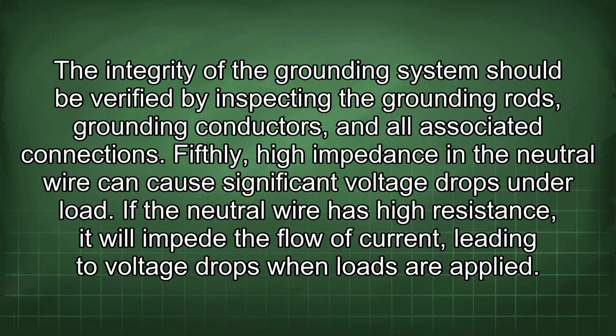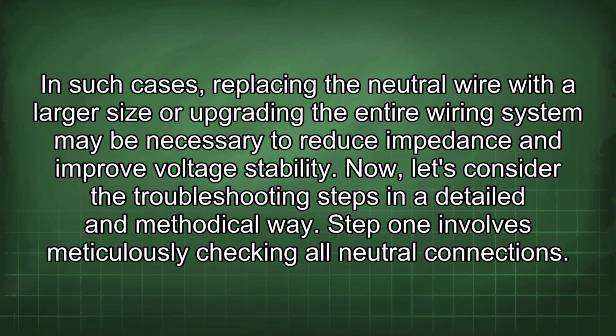Fifthly, high impedance in the neutral wire can cause significant voltage drops under load. If the neutral wire has high resistance, it will impede the flow of current, leading to voltage drops when loads are applied. In such cases, replacing the neutral wire with a larger size or upgrading the entire wiring system may be necessary to reduce impedance and improve voltage stability.